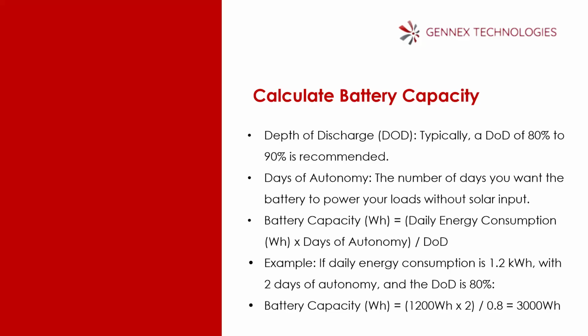Then battery capacity in watt hours equals daily energy consumption multiplied by days of autonomy, then divided by DOD. For example, if daily energy consumption is 1.2 kilowatt hours with 2 days of autonomy and the DOD is 80%, then the battery capacity in watt hours equals 1,200 watt hours times 2, which is the number of days. Then you divide your answer by the DOD, which is 80%, now 0.8, and you get 3,000 watt hours, which is 3 kilowatt hours. That's the capacity of the battery that's going to power that load successfully based on the timing of the run.